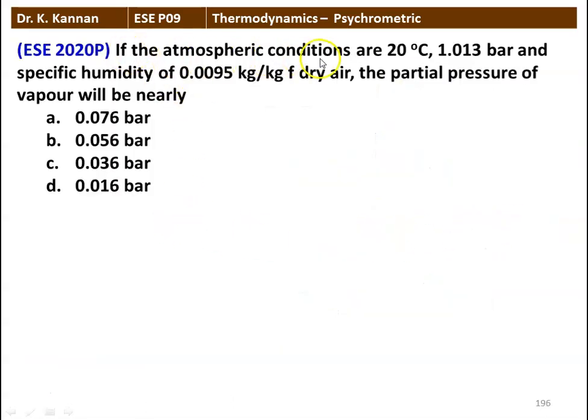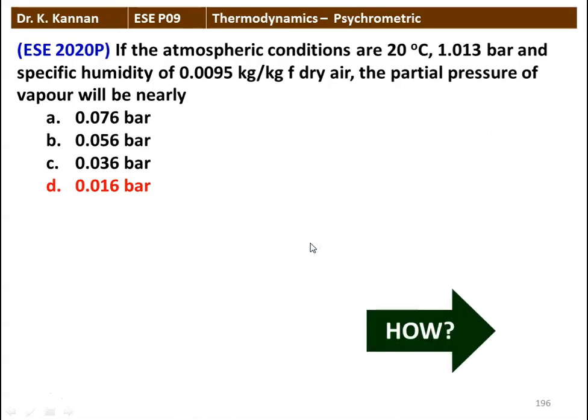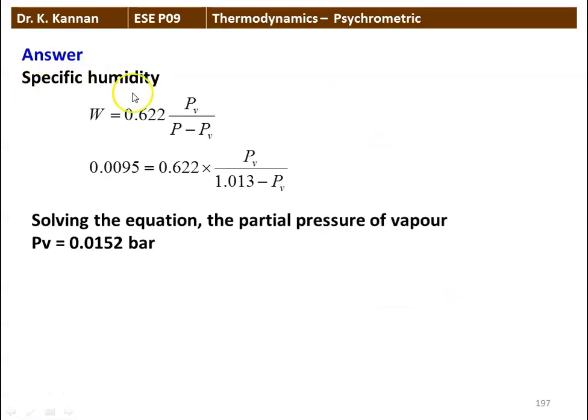Next question: atmospheric conditions are 20°C and 1.013 bar with specific humidity of 0.0095 kg/kg of dry air. Find the partial pressure of water vapor. Using W = 0.622 × PV / (P − PV), substituting 0.0095 = 0.622 × PV / (1.013 − PV), solving gives partial pressure of water vapor = 0.0152 bar. The correct answer is 0.016 bar.